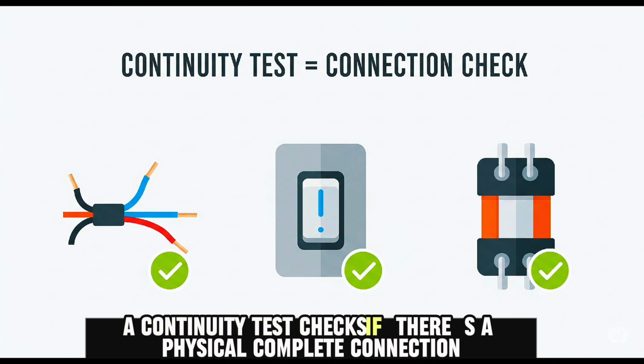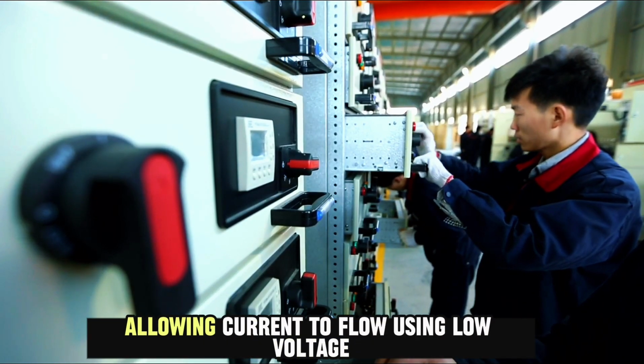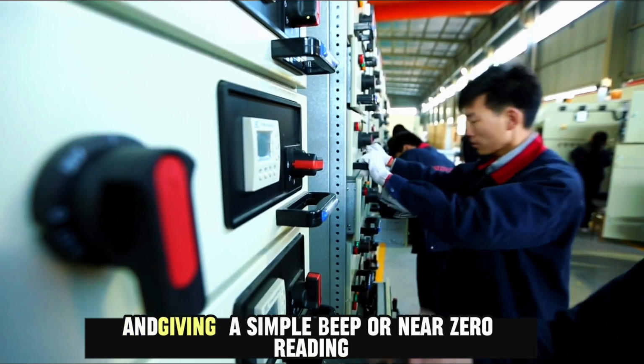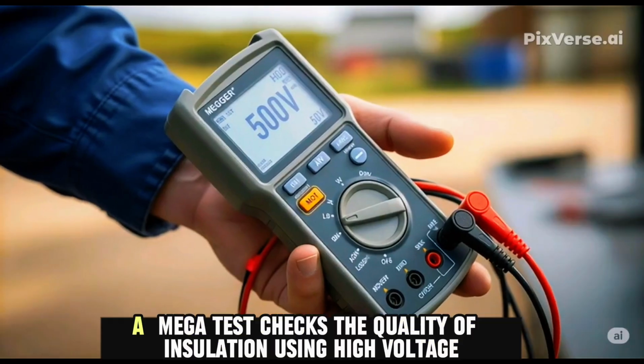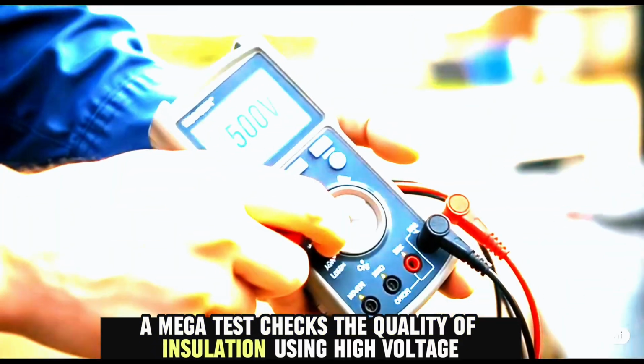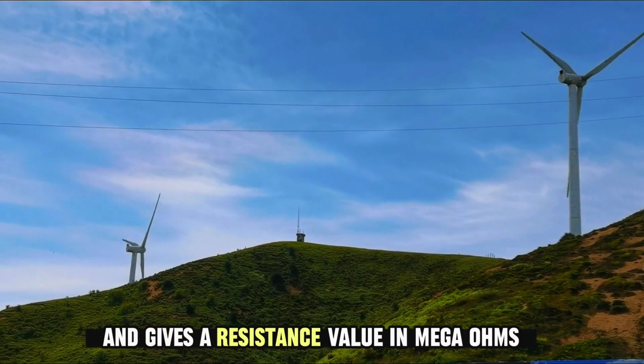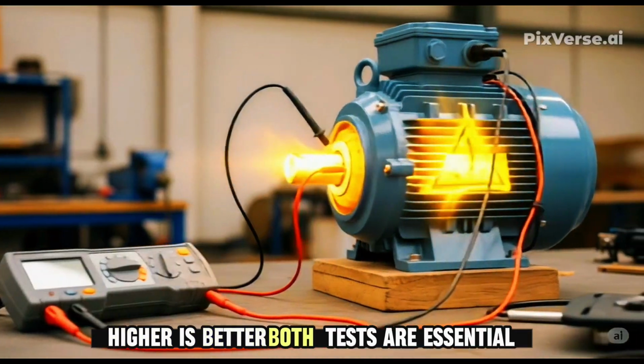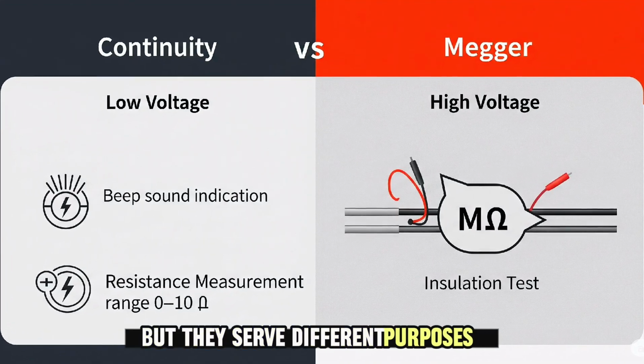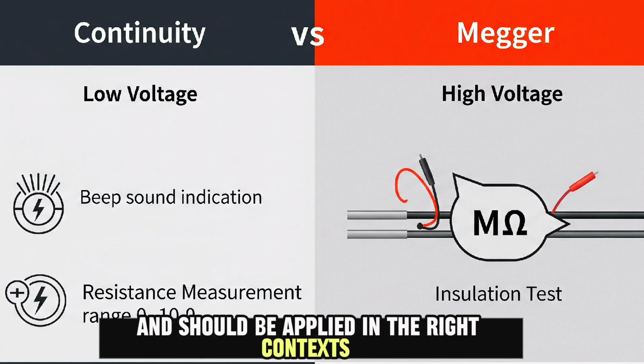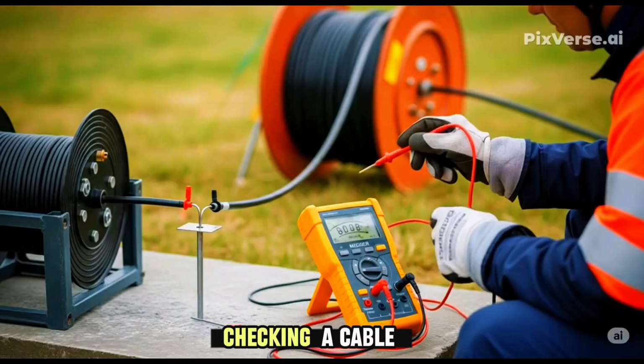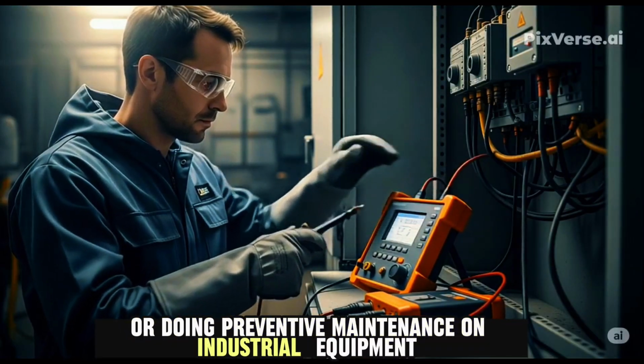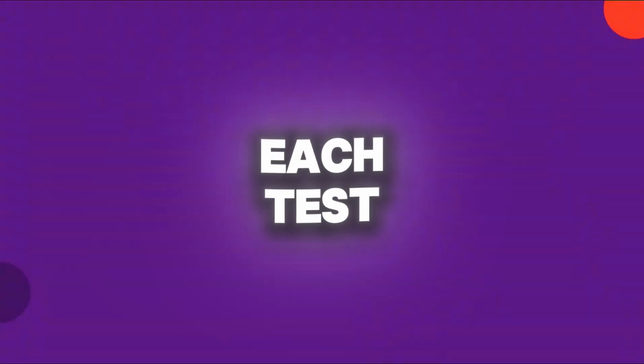So, to sum it all up, a continuity test checks if there's a physical, complete connection allowing current to flow, using low voltage and giving a simple beep or near zero reading. A Megger test checks the quality of insulation, using high voltage and gives a resistance value in mega ohms. Higher is better. Both tests are essential, but they serve different purposes and should be applied in the right contexts. Whether you're diagnosing a motor, checking a cable, or doing preventive maintenance on industrial equipment, knowing when to use each test could save you time, prevent accidents, and maintain a higher standard of electrical safety and professionalism.